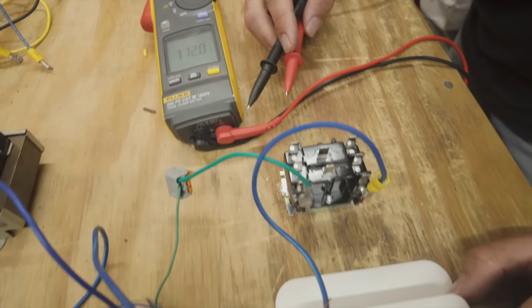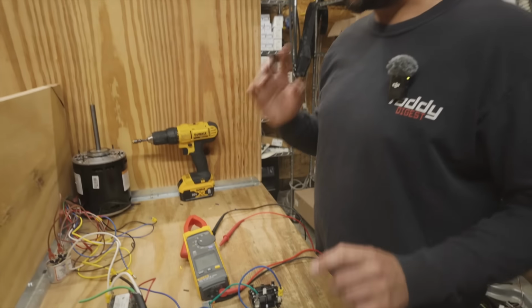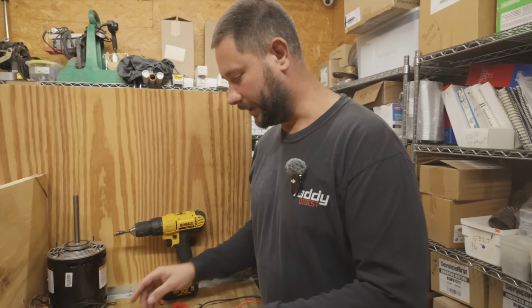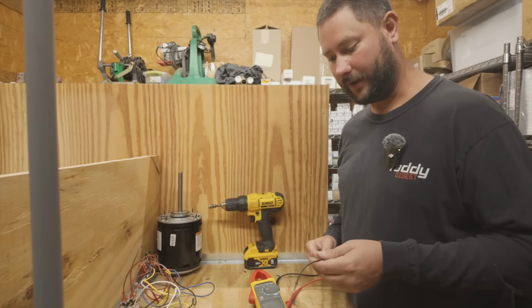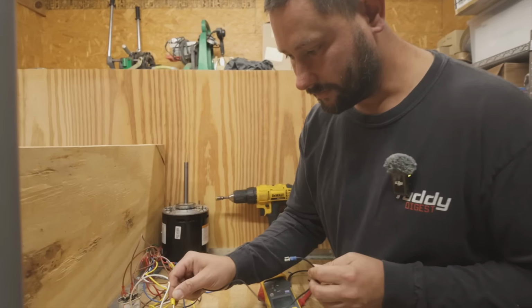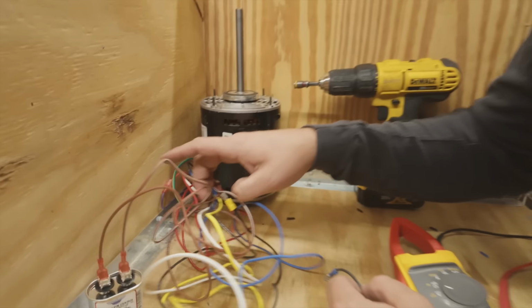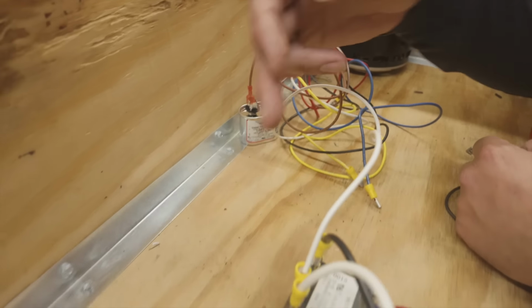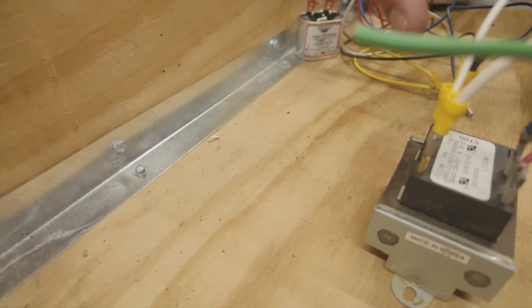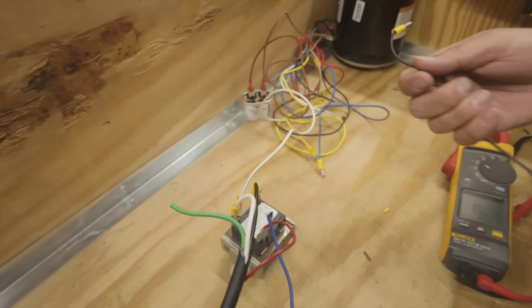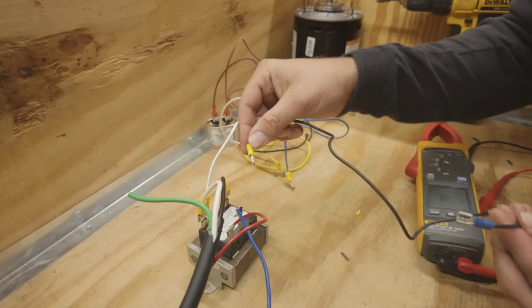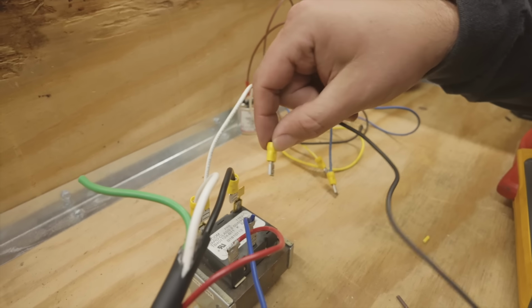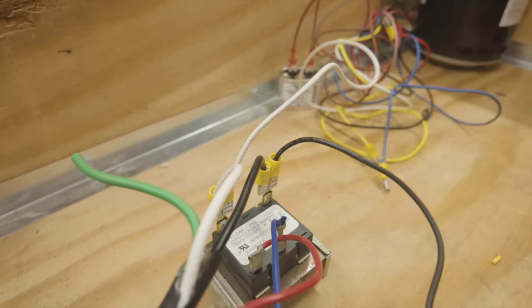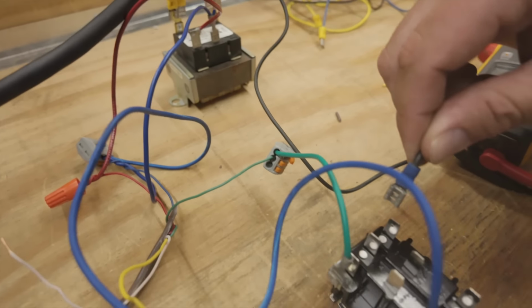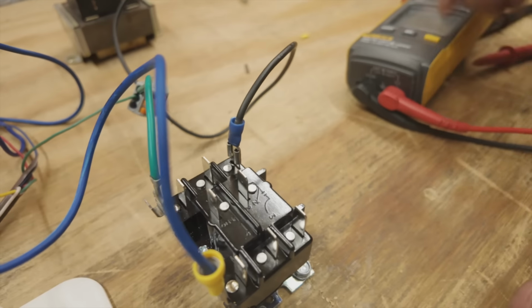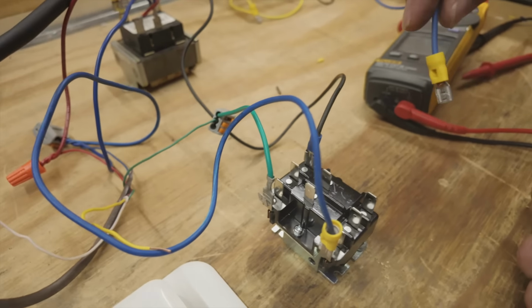All right, now here's what we're going to do. We're going to wire up our fan motor. So I'm going to wire up. I got to have hot coming in. So you can see for our fan motor, we've got one side of the line going to one side of our power. The other side of the power is going to come from this side of the transformer. Be very careful when you're touching wires when they're hot. Got to be careful. We're going to go into this normally open relay. Boop.